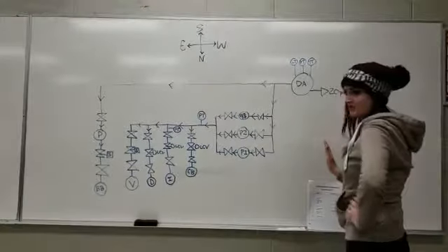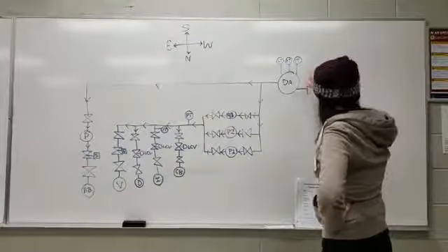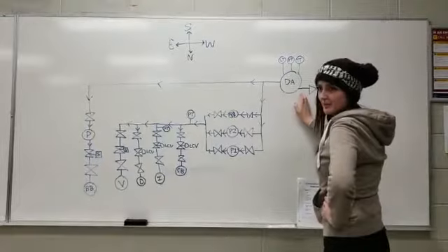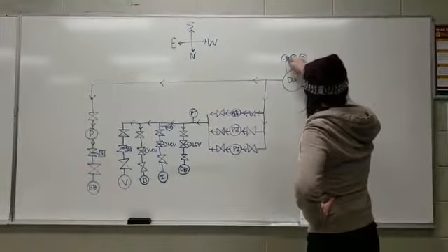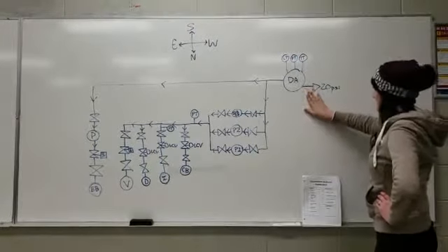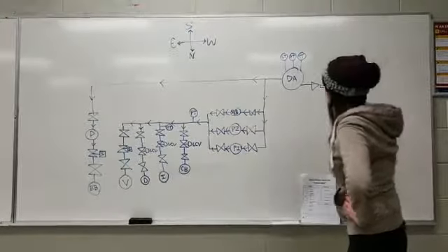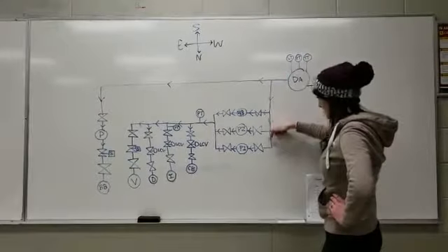And then looking at our blanket boiler feed water, we'll start at our DA, because this is what feeds your boilers and your blanket boiler. And we have our level transmitter, pressure transmitter, and temperature transmitter. And then aside from that, we have our safety relief valve of 20 PSI. And then the flow of the water will come out of your DA down to your pumps.